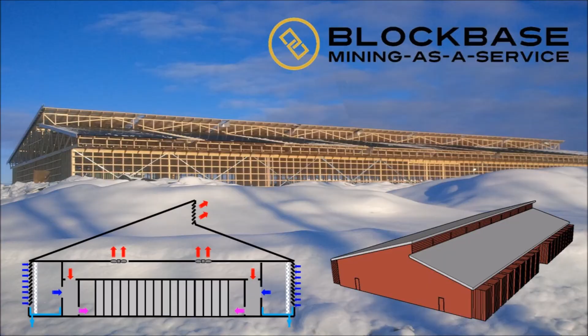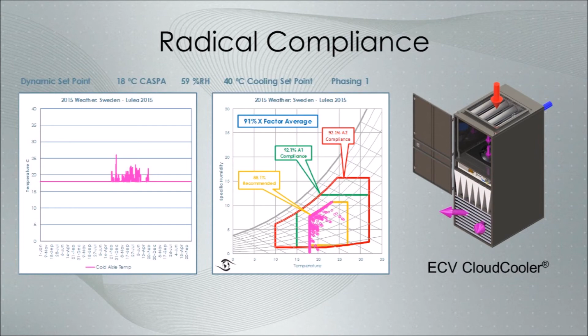That really simple device, forgetting about humidity, can give us really 100% compliance against some of the main ASHRAE standards. So this is how we create a huge density data center with massive airflows, massive power, but still give conditions equivalent to looking after your highest grade IT equipment in a tier 3 or 4 data center.